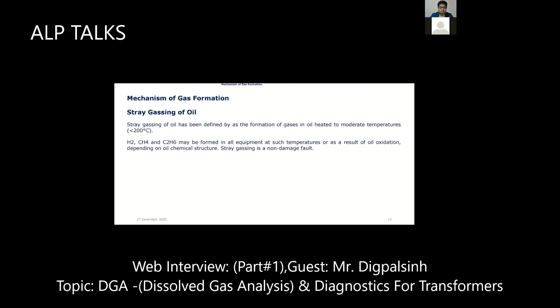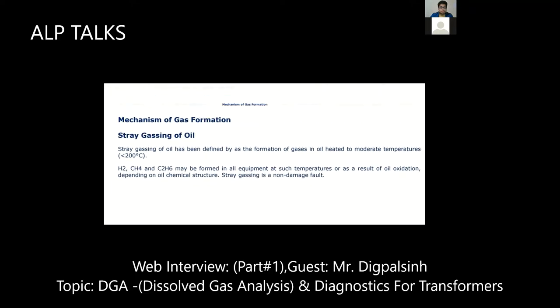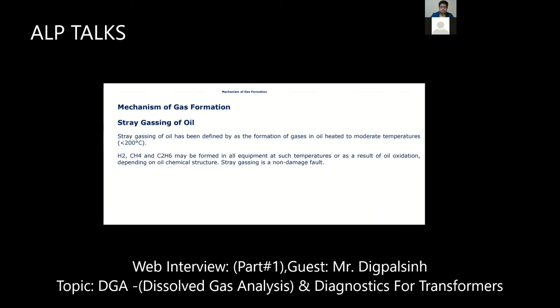Then the next gas formation is stray gassing. Stray gases are gases produced in the transformer by default. Even if no fault is there and the transformer is 100% healthy, some gases are still found inside the transformer, after some years of operation, say 3 to 4 years or a maximum of 5 to 6 years. In that case, you can just filter the oil, and these gases will be neglected. Mainly hydrogen is a stray gas for the transformer oil.